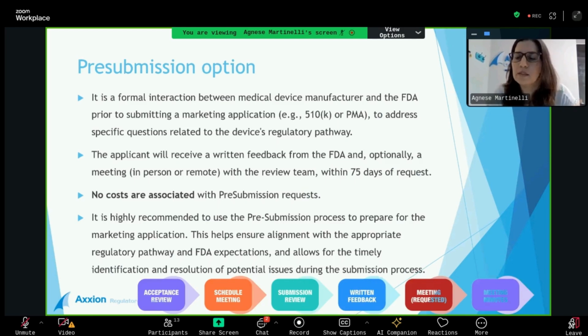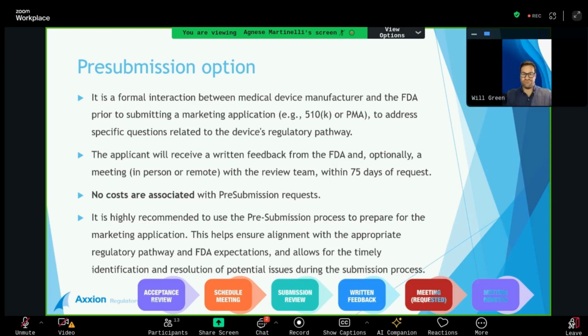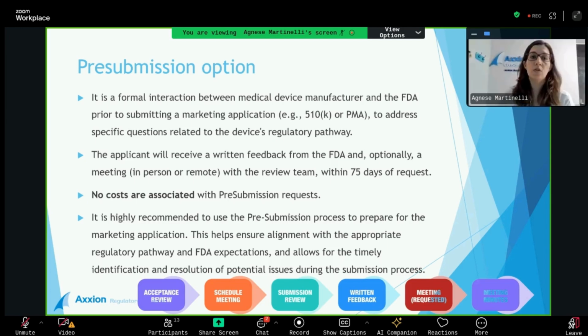Something that we highly recommend when you start considering submitting an FDA procedure, and to classify your device under the FDA framework, is to consider the pre-submission option, which is a formal interaction between the manufacturer and the FDA to address some specific questions related to the regulatory pathways. What we are looking for at this point is to agree on a good or adequate regulatory strategy and to be confident in it.